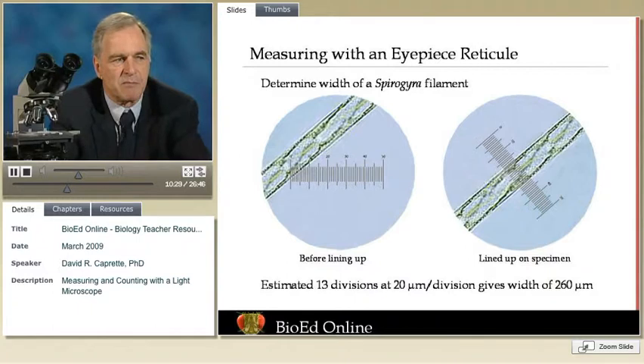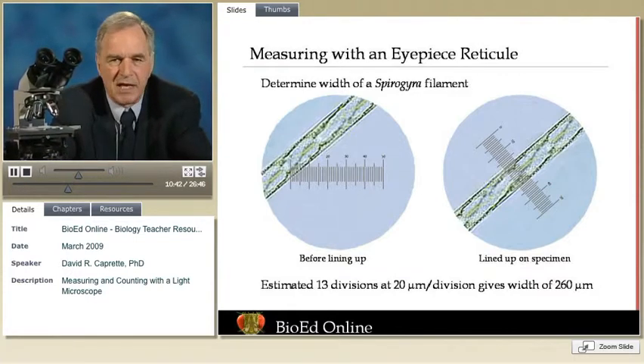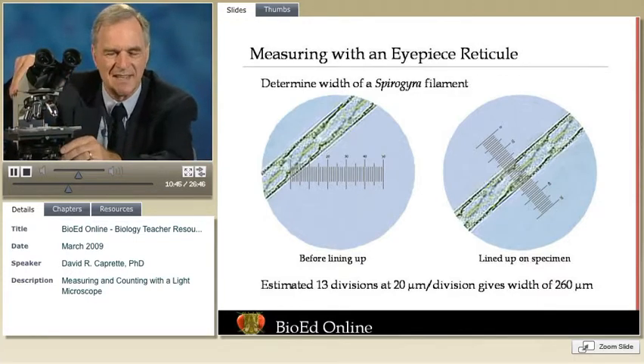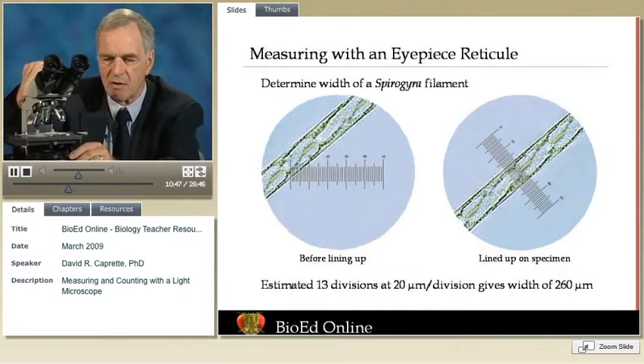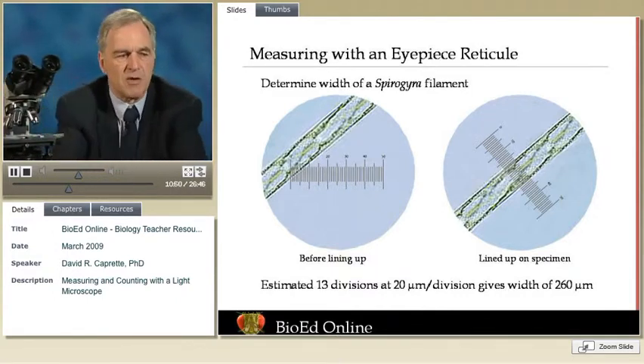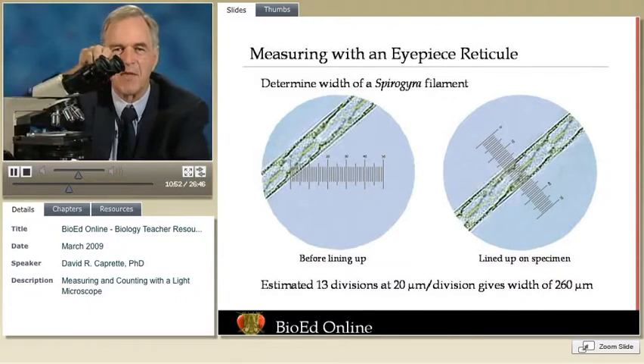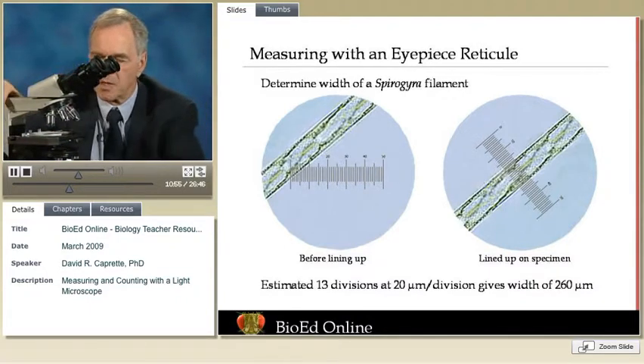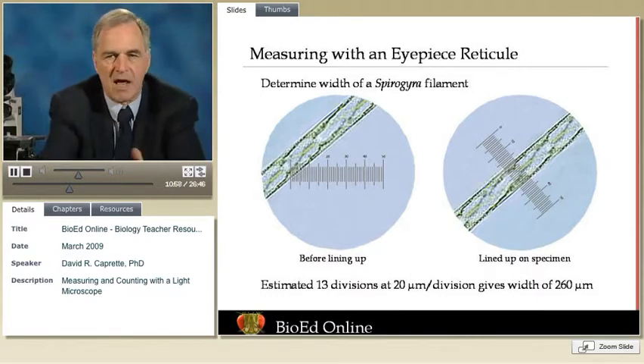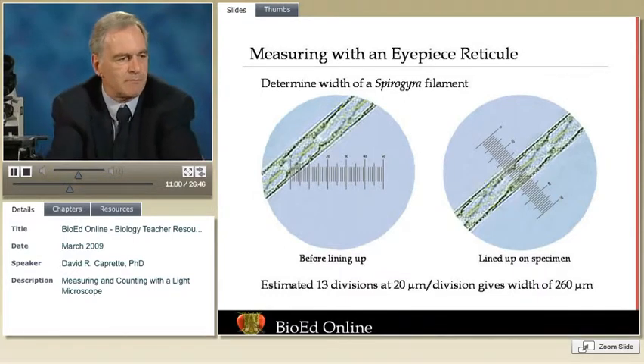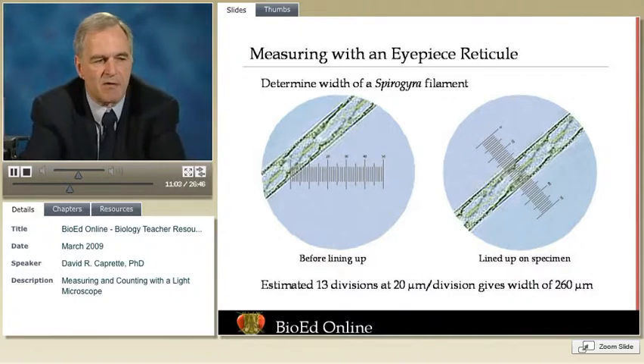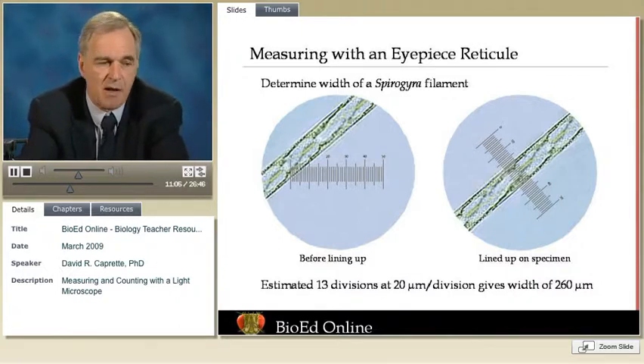In the example of a spirogyra filament, we wanted to measure the diameter of the filament. I called it width, but it's really a diameter. Remember, we're working in three-dimensional space. Spirogyra is in the field at an angle, and we can't change that angle, but we can certainly position the filament across the center of the field of view, and then rotate the ocular so that the reticle lines up perfectly with the filament, and then count the number of divisions and get an estimate. 13 divisions, for example, at 20 micrometers per division gives us a width of 260 micrometers.